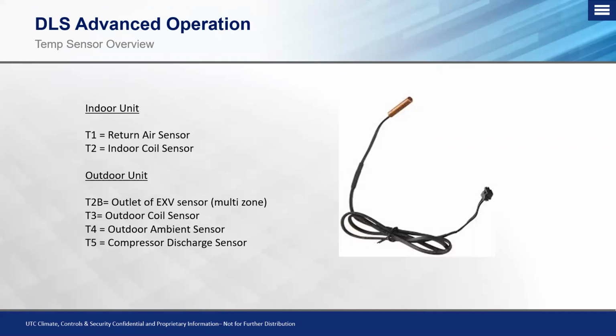Okay, so in the indoor unit, if you have a true ductless system, which means a true ductless indoor unit, a high wall, a cassette, a horizontal ducted, floor consoles, underceilings, true ductless indoor units, not hybrid scenarios where we're taking a residential fan coil and bridging it with a ductless outdoor unit. So this is true ductless one-to-one or true ductless multi-link systems. All of those indoor units have two main sensors. The first one is T1, and that is your return air sensor or the room temperature sensor. The other sensor in that indoor unit is going to be your T2, which is your indoor coil temperature sensor.